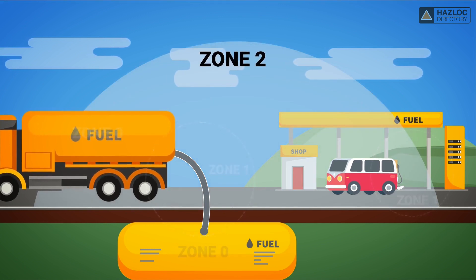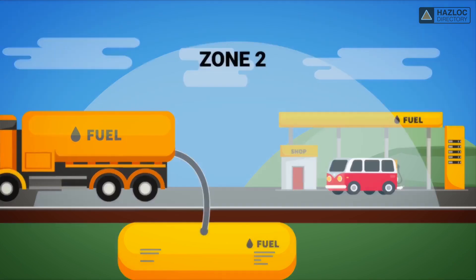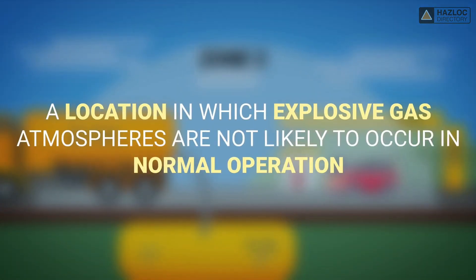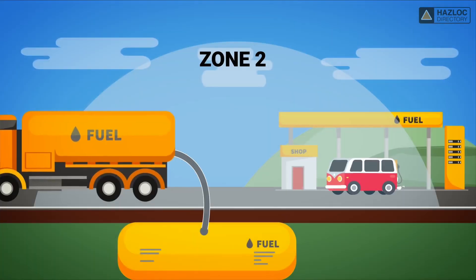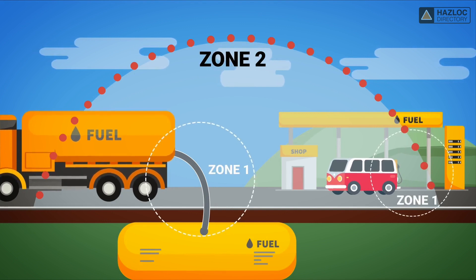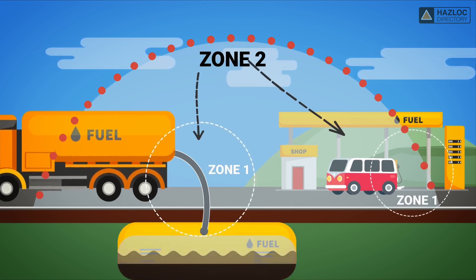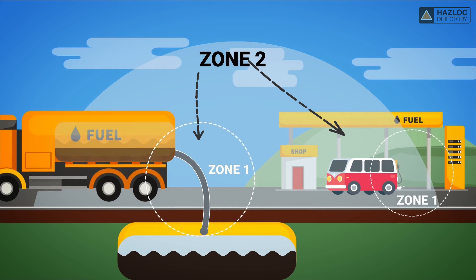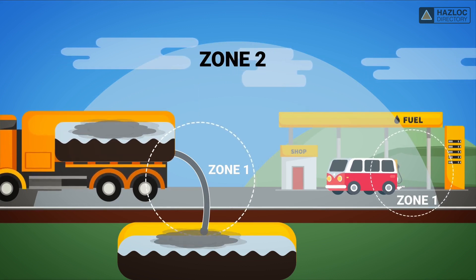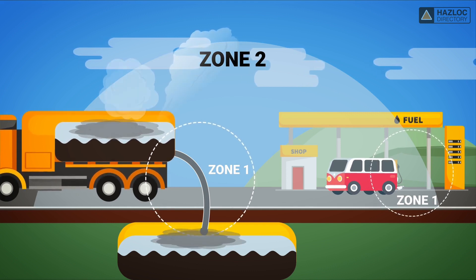In this animation, our focus is on the Zone 2 classified areas. Zone 2 is a location in which explosive gas atmospheres are not likely to occur in normal operation, and if they do occur, they will exist for a short time only. Zone 2 includes the area adjacent to a Zone 1 location from which gas-explosive atmospheres could be communicated. In our example of the tank, the area identified as Zone 2 is outside of and immediately adjacent to the Zone 1 area.